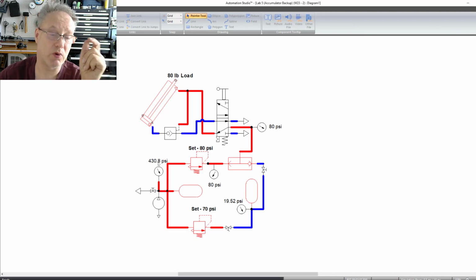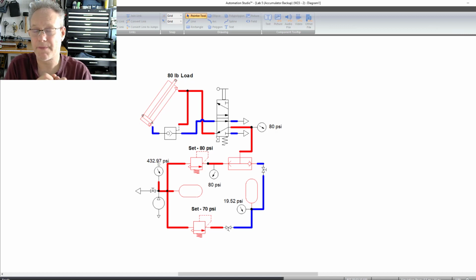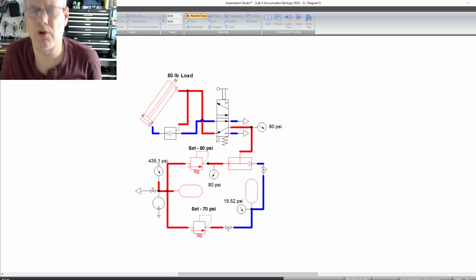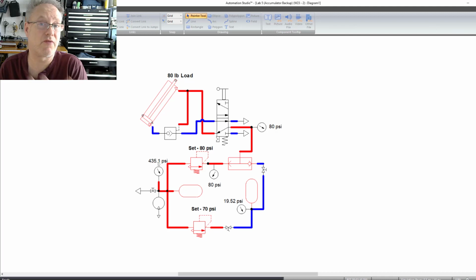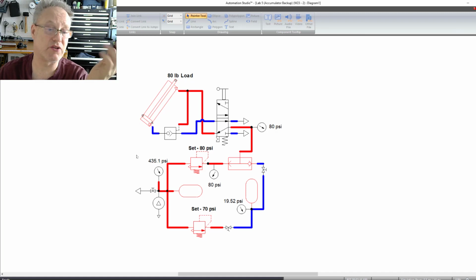Again, this is going up and up and up. What's going to happen is that you have a pressure switch on your electric motor, or whatever the prime mover is, that's running the compressor. It could be a gas motor, a diesel motor. There's going to be some kind of switch that says, hey, the pressure has reached this amount, the switch will open. Again, that's adjustable with a screwdriver. When the switch opens, it's going to turn your prime mover off, in this case an electric motor. The electric motor could be DC, could be AC, could be three-phase AC, a really big, strong motor, or just a 12-volt or 24-volt DC motor, whatever. And again, it's just a switch that opens and closes. So you're not going to get these ridiculously high numbers.